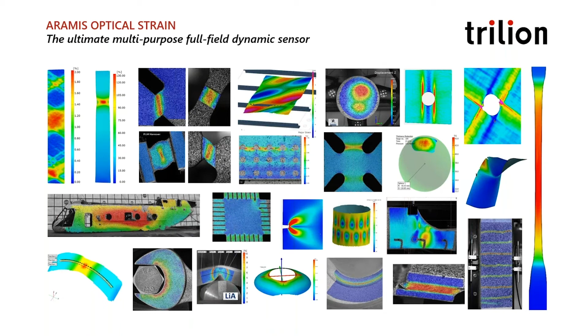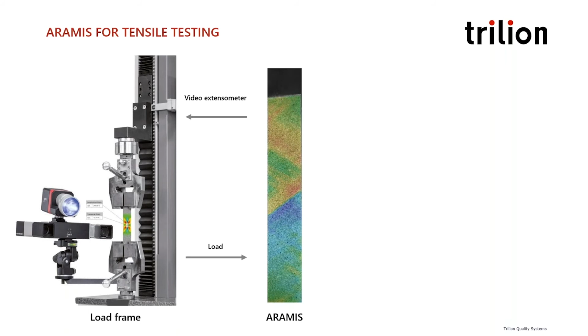And what we're doing is we're pulling a sample in tension and tracking the strain behavior over the course of the test. So we see all the colors changing on the sample to the right side as it's being pulled. And those are unique strain concentrations that are propagating throughout the specimen until it finally yields. This is actually a metal sample. And so what we might be anticipating in this case is Lüders bands that are propagating throughout the specimen until it finally fails. This sort of output is only a possibility with the Aramis system. You'll be able to pick up on those strain signatures throughout the sample, whereas a simple strain gauge would have a very hard time reading that.